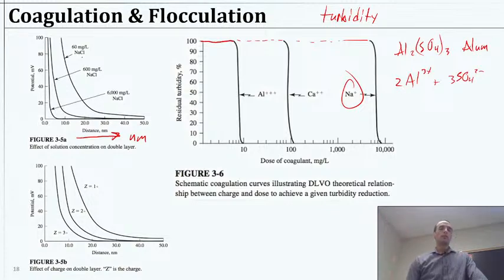In this first one, with 60 milligrams per liter of sodium chloride, we can measure a pretty strong charge. Let's call, for example, 30 millivolts a decently strong charge that should probably keep particles separate from each other. So we see a reasonably strong charge with 60 milligrams per liter of sodium chloride all the way out near 20 nanometers.